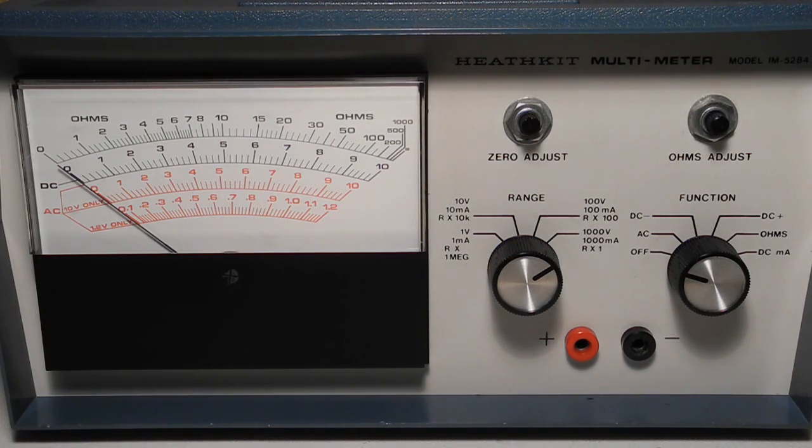It can measure DC current at four ranges from 0 to 1, 10, 100, and 1,000 milliamps at plus or minus 4% accuracy. And finally, it can measure resistance with ranges of R times 1, times 100, times 10,000, and times 1 million at plus or minus 3% accuracy.